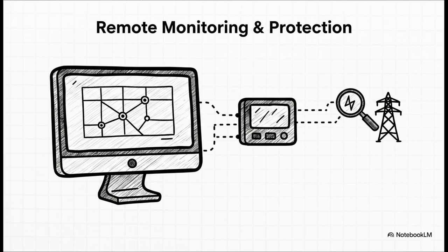We'll coordinate advanced protection schemes for the lines, the bus bars, and the transformers. You'll learn exactly how to configure sophisticated numerical relays for both distance and differential protection. These intelligent little devices are programmed to detect abnormalities and isolate catastrophic faults in literal milliseconds.